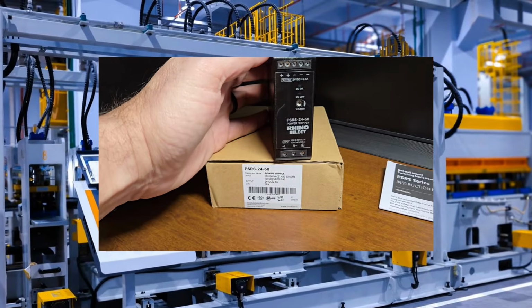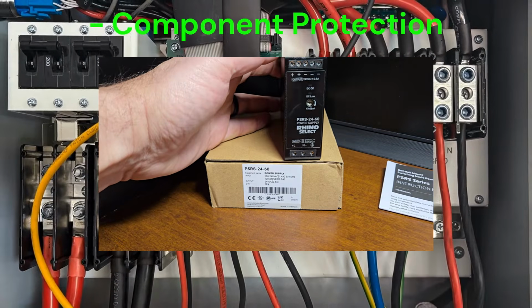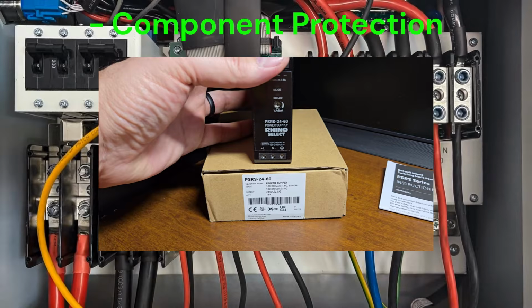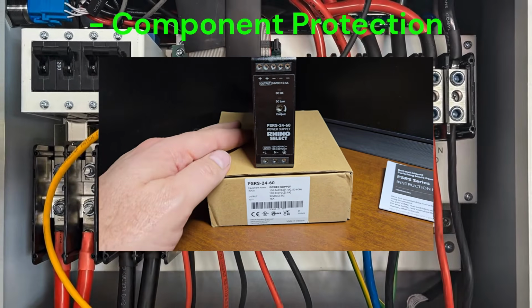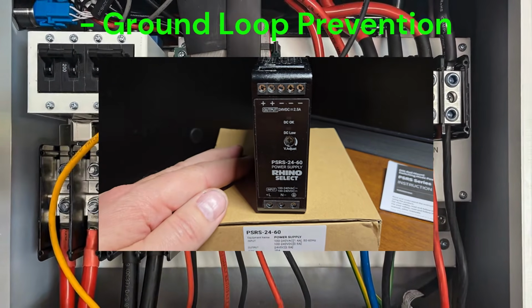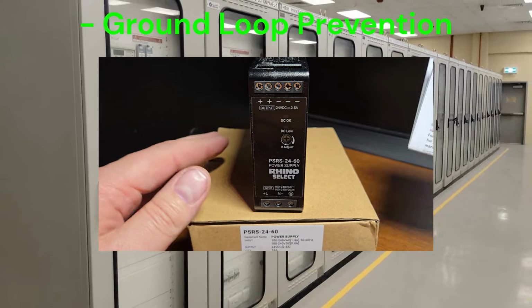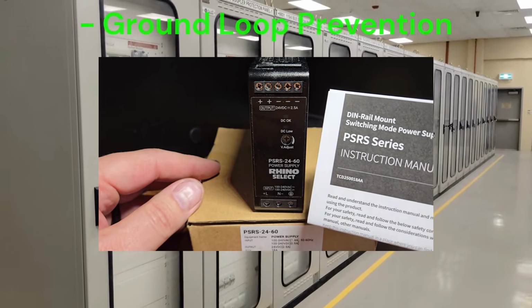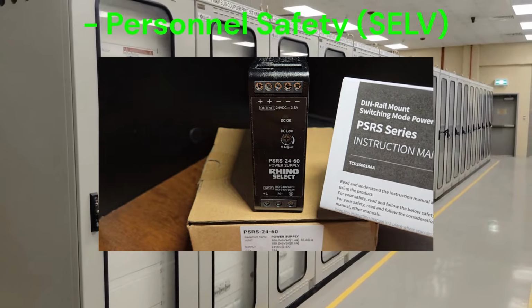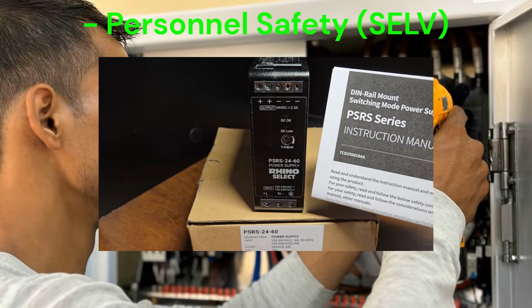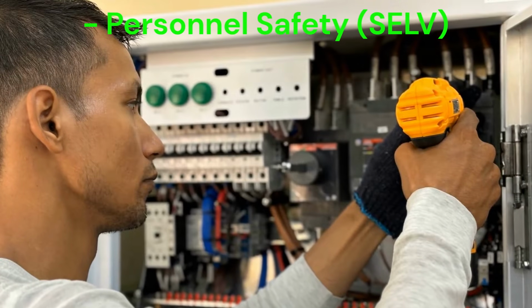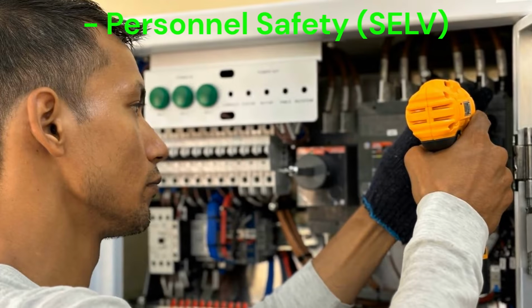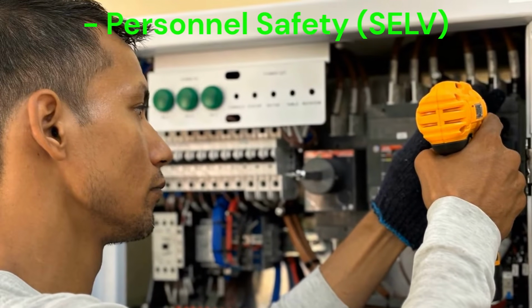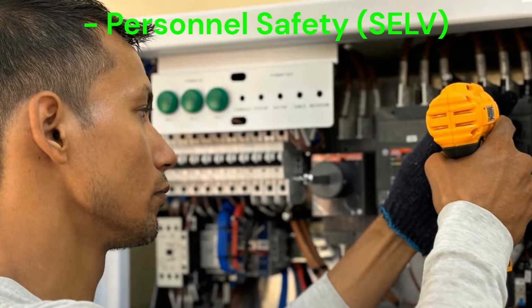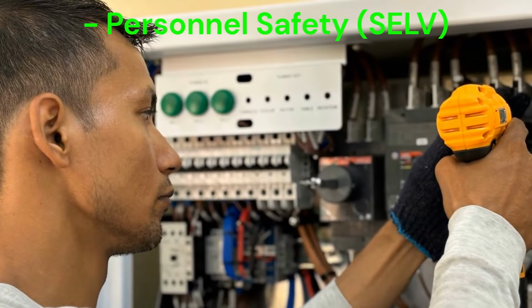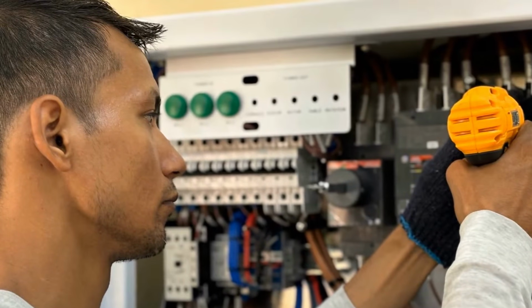Why this matters for your low voltage circuits? Component protection. It acts as a firewall. Faults on the main side do not propagate to the DC side. Ground loop prevention. It helps prevent noise issues caused by differences in ground potential across the facility. Personnel safety, SELV. By isolating the output from dangerous line voltages, the 24V DC side becomes a safety extra low voltage, SELV circuit, which is significantly safer for technicians to work around for maintenance and troubleshooting.